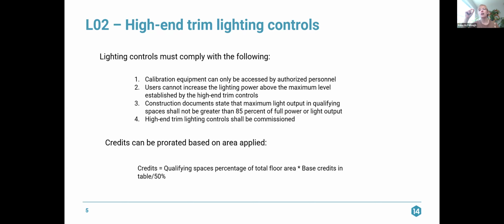And the construction documents must state that the maximum light output in these spaces must not be greater than 85% of full power or light output. So again, rather than that 90% maximum, it would be 85% to achieve credits under credit section L02. They also have to be commissioned per section C408.